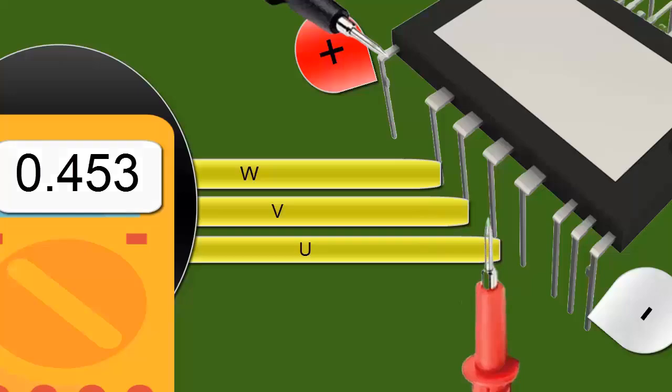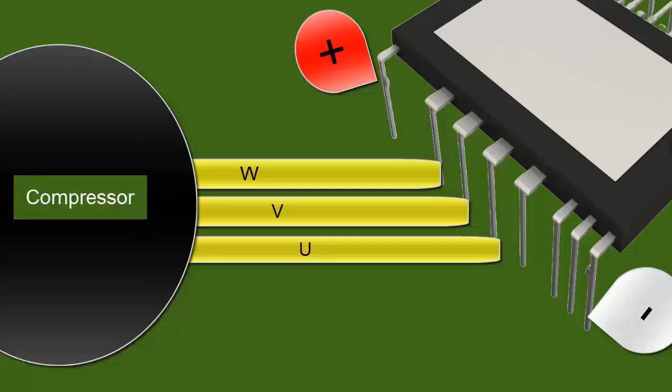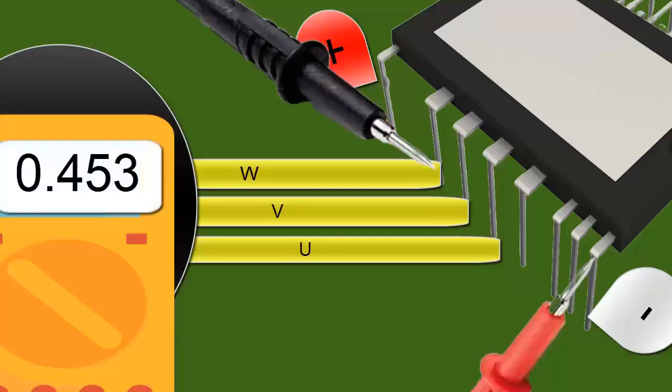Let's proceed with the integrity test of the last three diodes. Place the red probe of the multimeter on the negative input of the IPM electronic circuit.